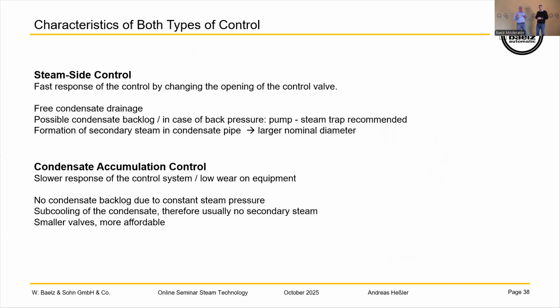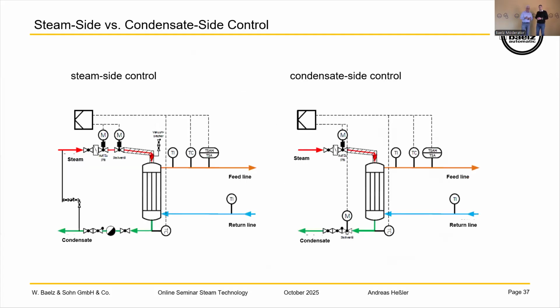The disadvantage of a steam side control is that you have a fast response of the control, and that means you have more wearing of the components, because you always have a big heat on it. If you do it with the condensate, you're controlling the condensate level, because the steam is always on the top and it's not going less or more. Also, of course, we have more efficiency because a control valve on the bottom for the condensate is much cheaper, and you need no strainer or steam trap on the inlet. You see on the left picture, we need another steam trap on the inlet of the condensate heat exchanger.